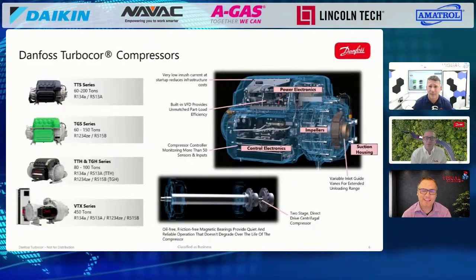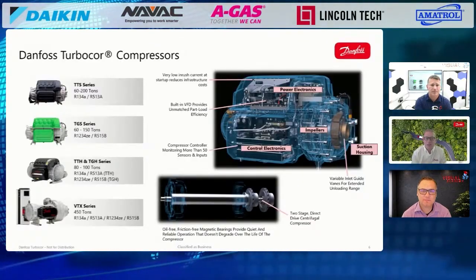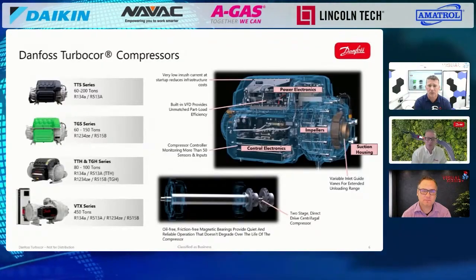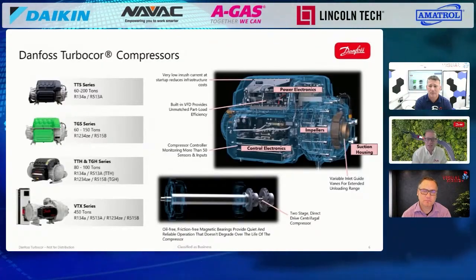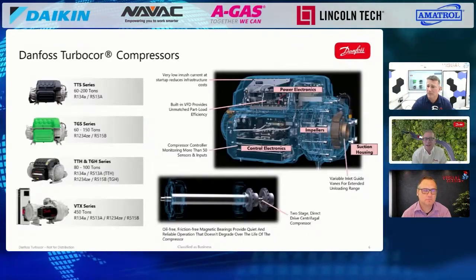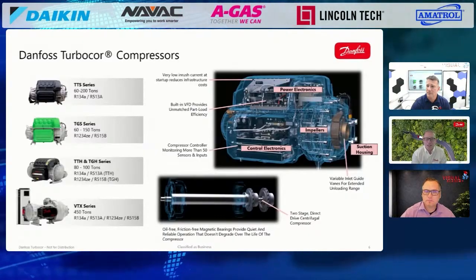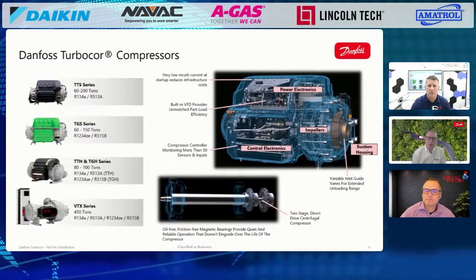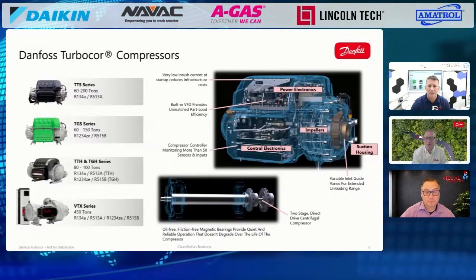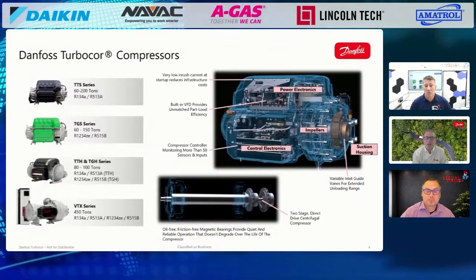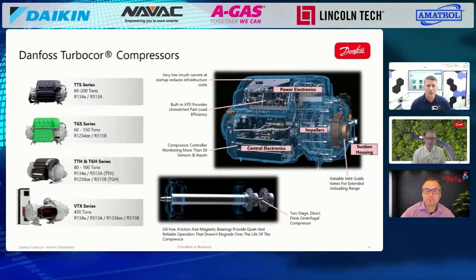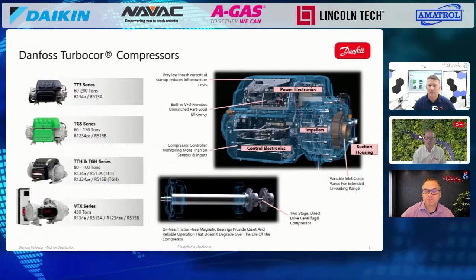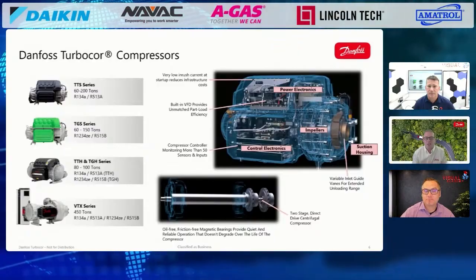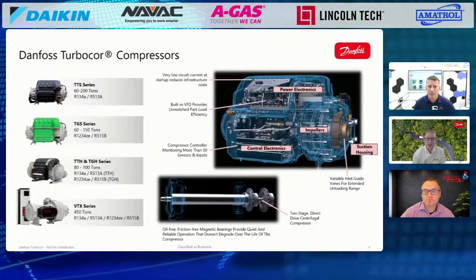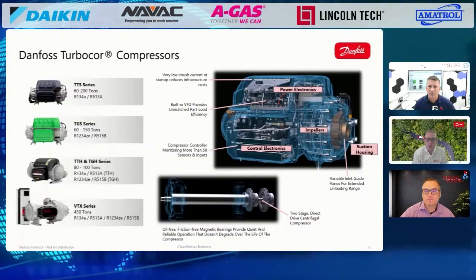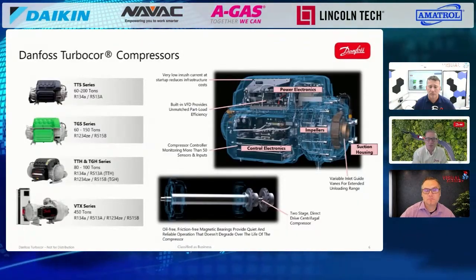So what is Turbocor? We pride ourselves on being the pioneer in oil-free magnetic bearing centrifugal compressor technology for HVAC. The analogy I've heard, and I think is super fitting, is that a Turbocor compressor is more like a computer acting as a compressor than a traditional mechanical compressor. We're combining mechanical, electrical, and software together to function as one unit within our compressor. As you can see here, this is a cut shot with see-through covers to show the different sections of the compressor.